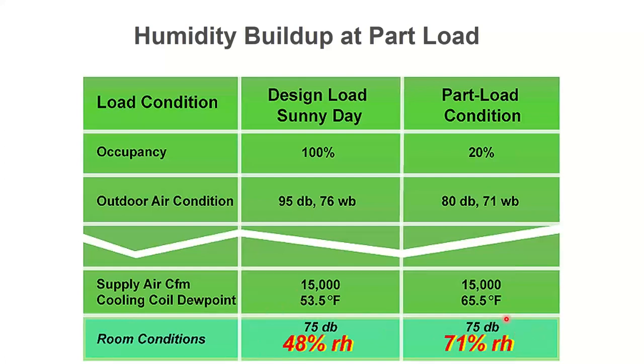So that means I'm going to be getting a dew point of 70 something, 50 something, 70 something, 50 something, 70 something, 50 something, and it's going to average out to 65.5. And that's going to be pretty difficult to dehumidify with. And hence, I'm going to have a resultant humidity that's 71% in this space. Both spaces get 75 degrees because that's what they set the thermostat for. One of them just has a lot more humidity because it can't handle the part load condition very well. There's lots of ways to deal with that.